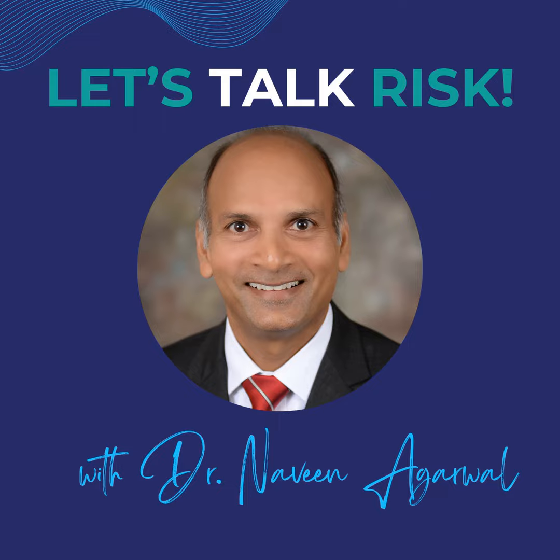Sure. This has been a great discussion and I would love to keep going. But I think the main takeaway is, when you think about AI, ML, automation, technology, and you're thinking about use-related hazards, make sure you're capturing and using the guidance documents that are out there, and they point to other reference resources for understanding those potential hazards that come with what I'm calling automation. Capture those in your risk file.